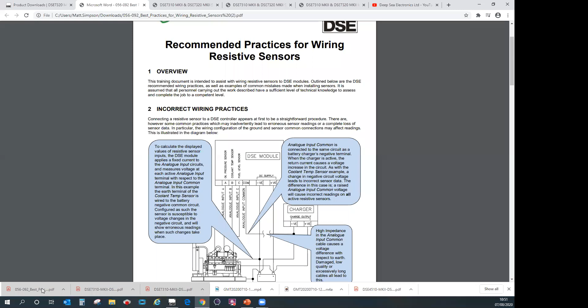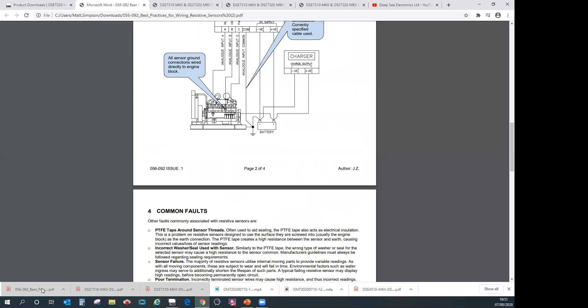So recommended practices for wiring resistive sensors just tells you how to wire a sensor, and it gives you an example of common faults. It mentions failed to stop on an oil pressure sensor. On a generator, it's difficult sometimes to know if the engine's running. On a car, you're moving; on a generator, it makes noise. But if you're not on site, or the controller's well away from the generator, you don't actually know if it's running. So you have indications of whether the engine's running, like oil pressure, frequency, or engine speed. If the oil pressure is stuck high, that indicates the engine's running, but it might be the case that the sensor's failed and stuck, say at 10 bar, making you think the engine's running when it's actually not. That gives you what's called a fail to stop alarm. It explains a little more detail about that.